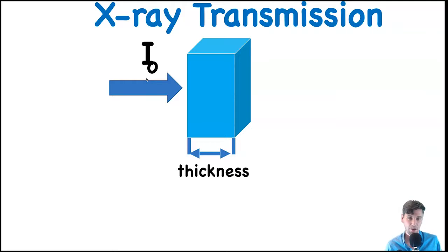On a standard X-ray system, you'll be looking at an array of energies from the highest energy, which is the keV corresponding to the kVp of the X-ray tube, all the way down to fairly low energies, but usually not down to zero, because the lower energies are typically attenuated by pre-patient collimators.